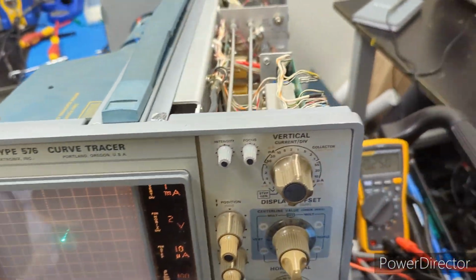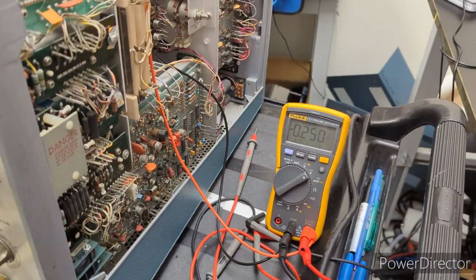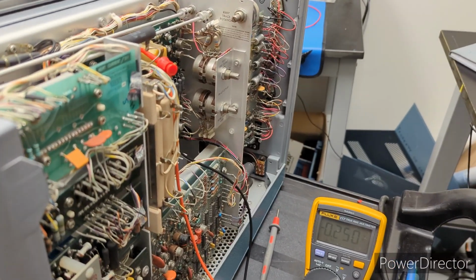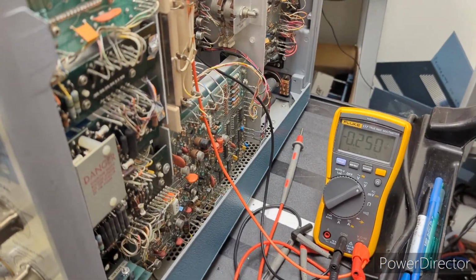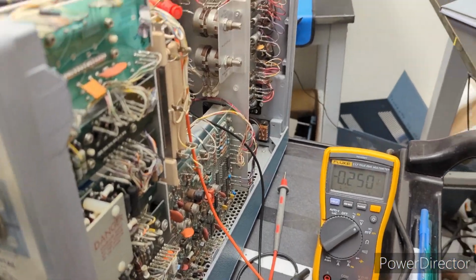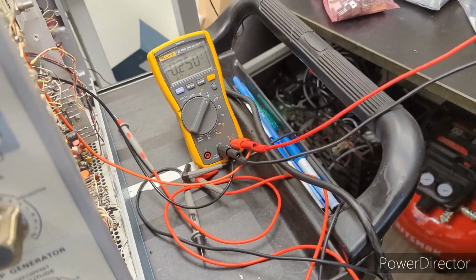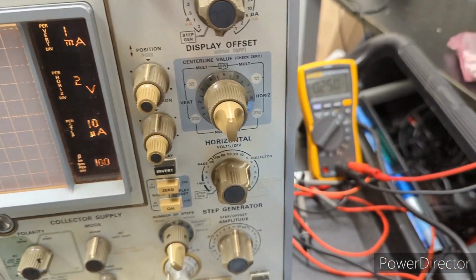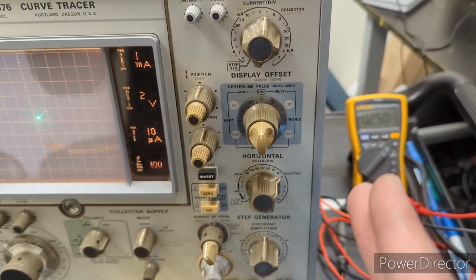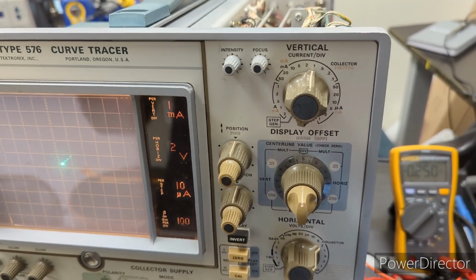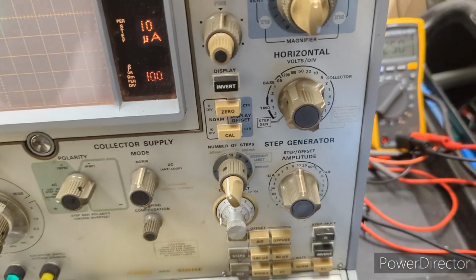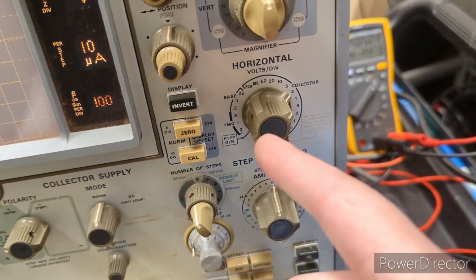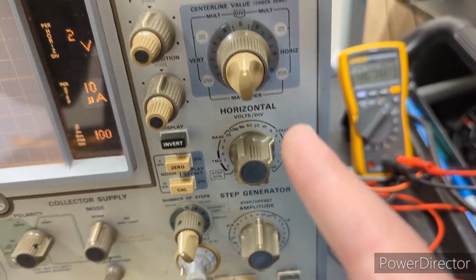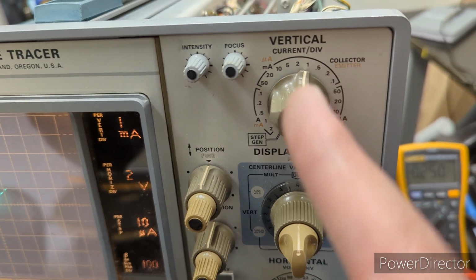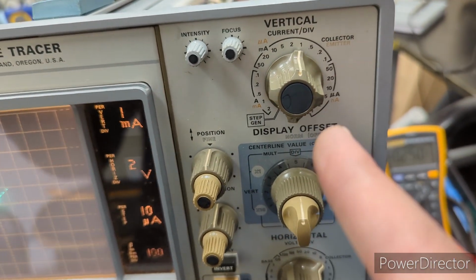Okay, so I actually just got done doing all of the low voltage and high voltage accuracy tests, and for ripple, everything looks great, nothing has changed. And then right after that test, they have you check a couple of the horizontal and vertical switch accuracies. So for the horizontal, they ask you to check settings 5, 2, and 1. And then for the vertical, 5 milliamps, 2 milliamps, and 1 milliamp. That's actually what we're checking right now.